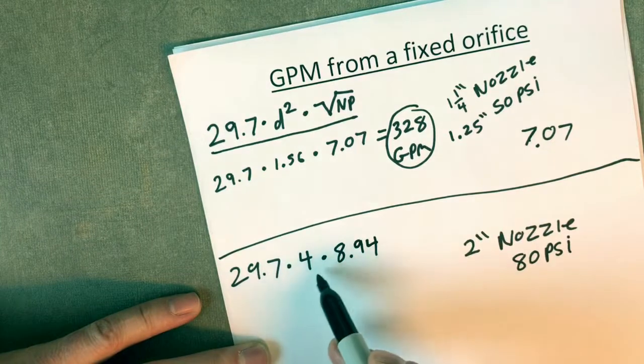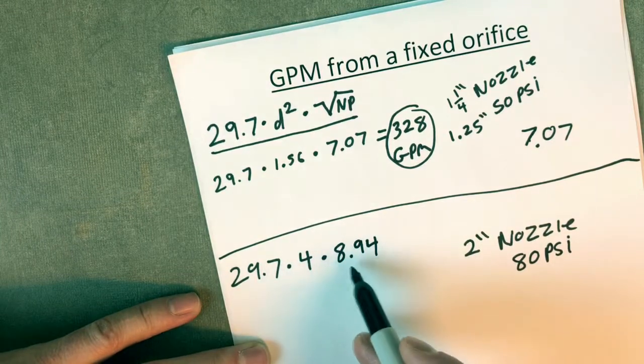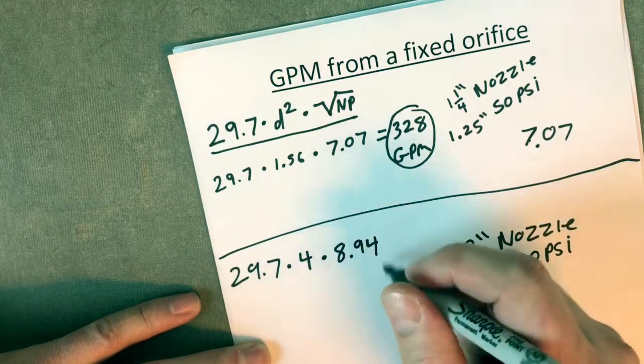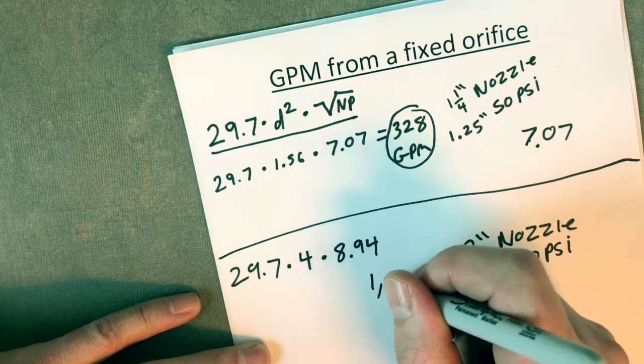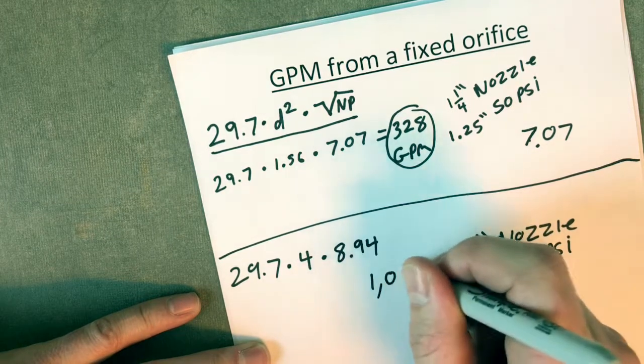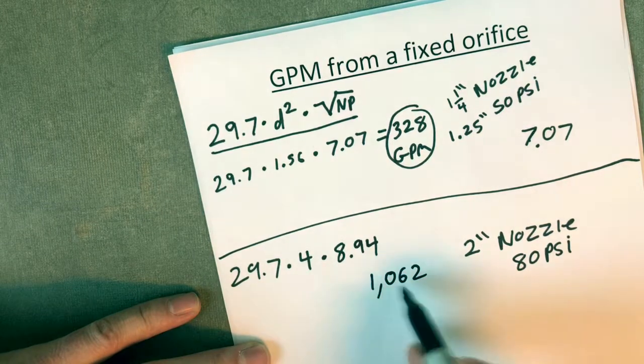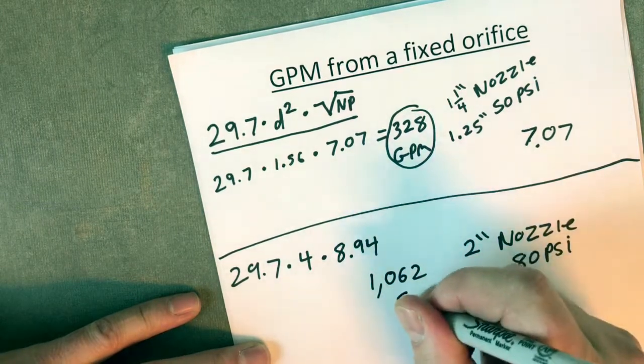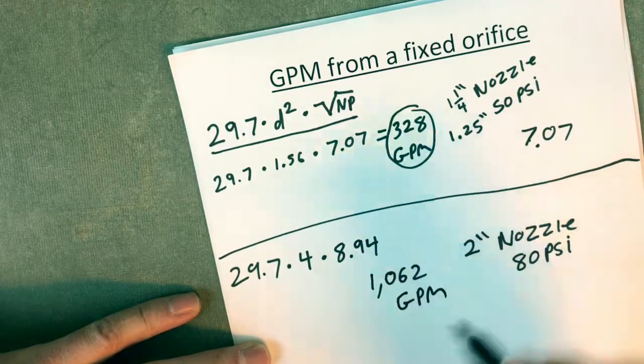29.7 times 4 times 8.94. If you calculate that out, it's 1062 GPM.